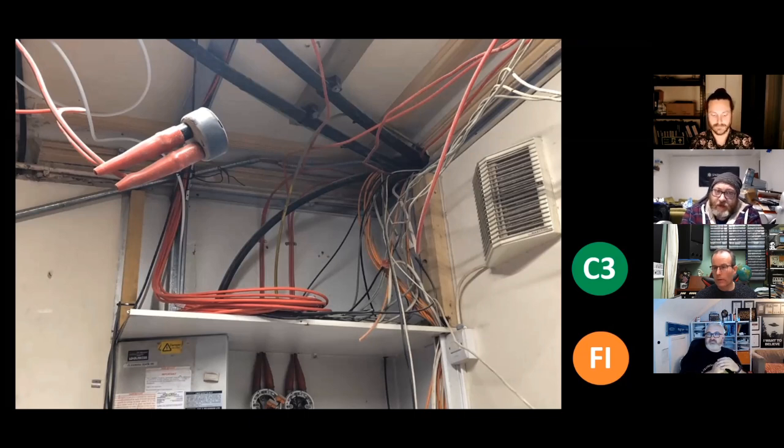This is a huge thing you just said. It's an operation, it's still running, you've still got the public, you've still got employees in this building, and any of these actions could seriously damage one of these conductors. Yep. Damaging their integrity, even creating a risk of electric shock. Demolition work should often be treated as live work. Many times it's not. Yes, I don't disagree with you. Your safe system of work should have these systems isolated, removed, or a temporary one put in place so that it can be safely stripped out as part of a soft strip, but not always the case. I'm going to end this poll now, so please vote quickly.